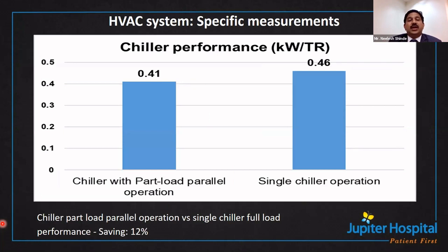Similarly, there is chiller part load parallel operation versus single chiller operation. If you have two chillers, instead of running a single chiller at 90%, 95% load, you run two chillers at part load with good efficiency in parallel operation, with two condenser pumps, two cooling towers, two secondary pumps and two primary pumps. Then there is a slight advantage of part load operation compared to single chiller operation. So these are things we can do in our day-to-day activity, and we can achieve savings there.